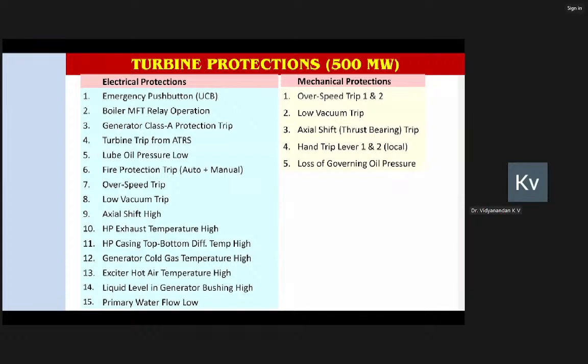With experience and the increasing size of the unit as well as the grid size, higher and more numerous protections were required. If you see a 250 megawatt machine designed some 20 years back, whereas the 800 megawatt commissioned today, you will find at least 5-6 protections are missing in the 250 megawatt machine. So almost every dynamic parameter associated with the turbine, whether vibration, pressure, temperature, flow, level, etc., every parameter is considered, and not only that, the speed.